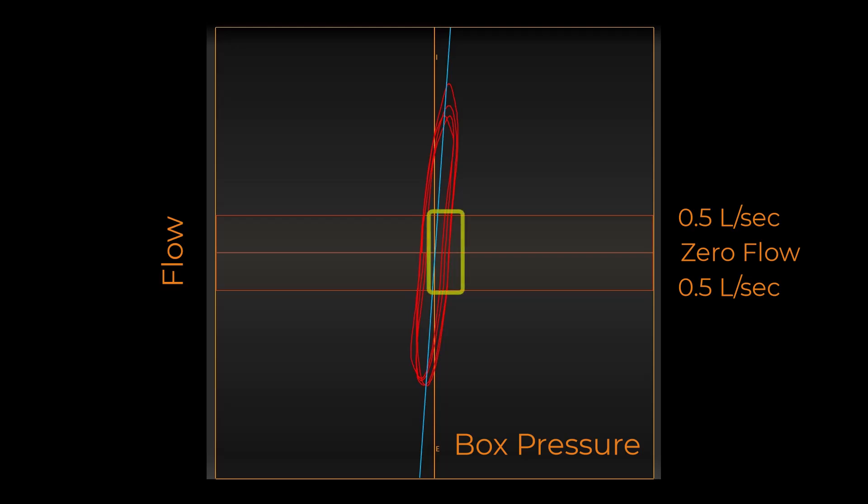Unlike lung volumes, airway resistance efforts take only the data between the two red flow lines and ignore the data above and below the flow lines when setting the line of best fit. Because of the limited data between the flow lines, adjusting the open shutter panting will become more frequent than the closed shutter breathing.